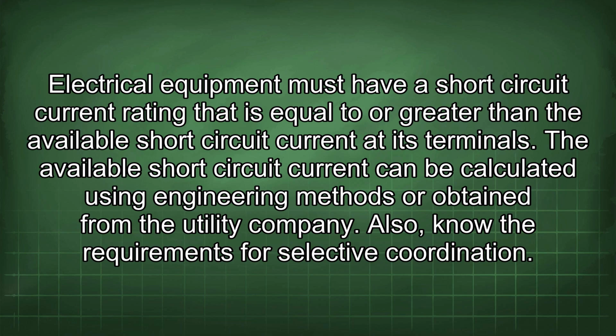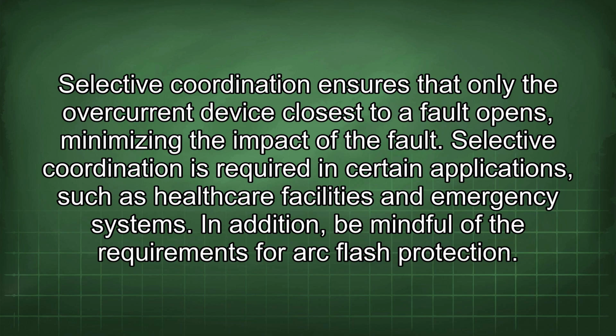Also, know the requirements for selective coordination. Selective coordination ensures that only the overcurrent device closest to a fault opens, minimizing the impact of the fault. Selective coordination is required in certain applications such as healthcare facilities and emergency systems.